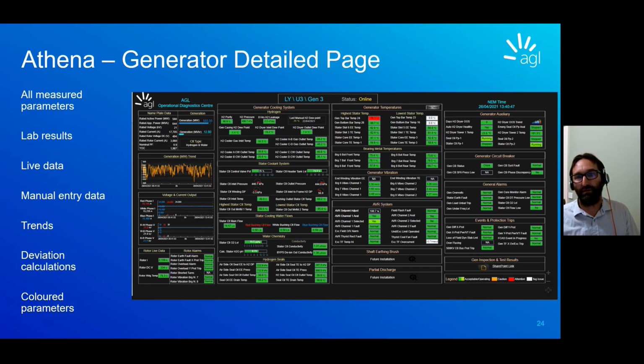What we've looked at here is the red on the highest data temp. We can see that the generator temp, rotor bar 74, is higher than normal. What we're trying to do here is show that we haven't diagnosed what the problem is, but we're alerting the engineer that this is different and it's higher than where you would normally like it to be.